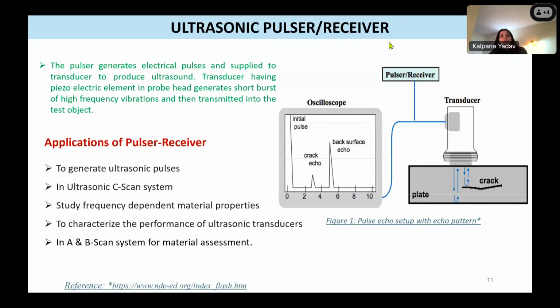So the pulser generates electrical pulses and supplies them to the transducer to produce ultrasound, the transducer having a piezoelectric element in the probe head that generates a short burst. So this is some kind of electronics. You need to figure out what frequency you're going to use, what gain you are going to use, what type of signals you're using, right?